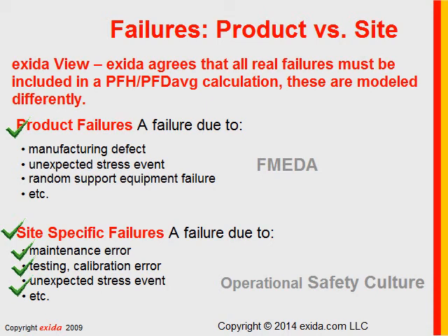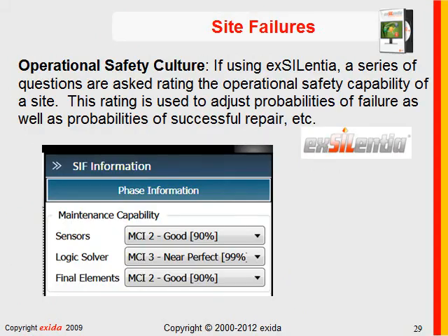The exida view is that all real failures must be included in a realistic PFD calculation, but we model them differently. We use the term 'operational safety culture.' We have a method to evaluate the operational safety culture of a company and use that model in our exSILentia tool to adjust failure rates, probabilities of successful repair, probabilities of successful proof tests, and other variables impacted by site-specific policy. This more accurate modeling gives credit to those doing a good job and properly penalizes those who are not.